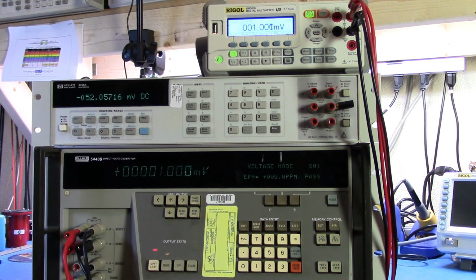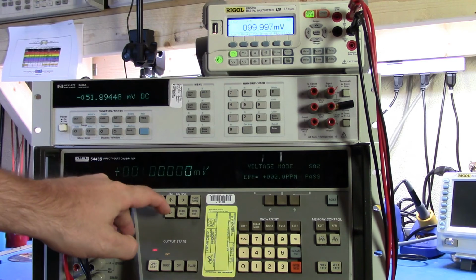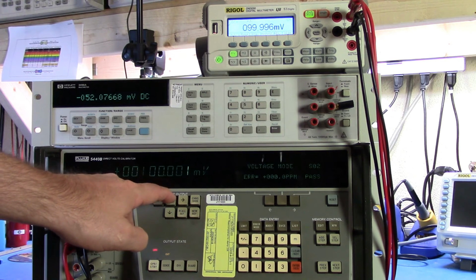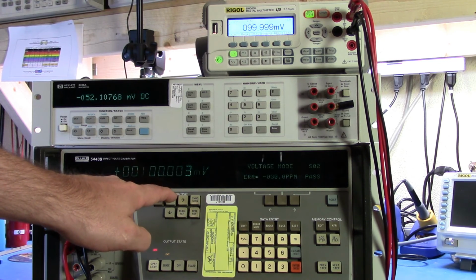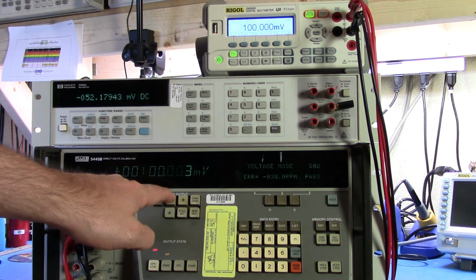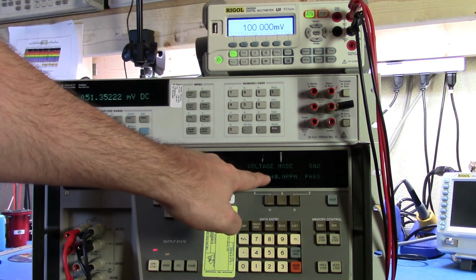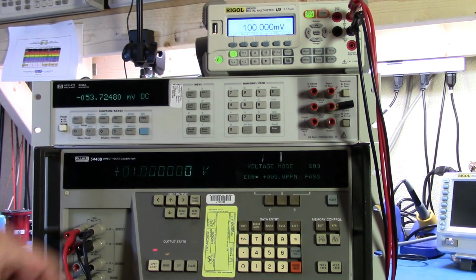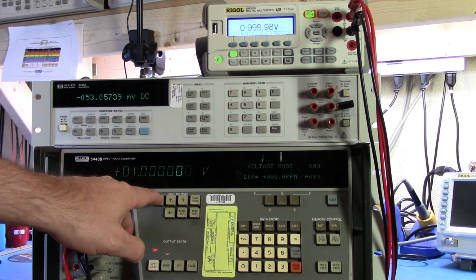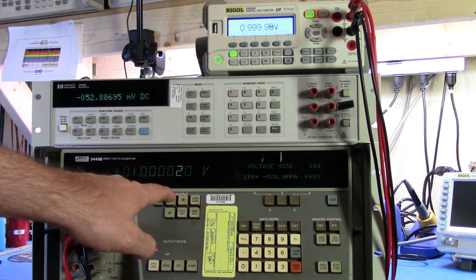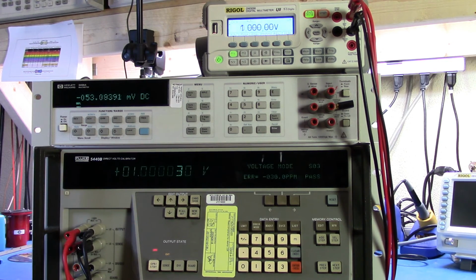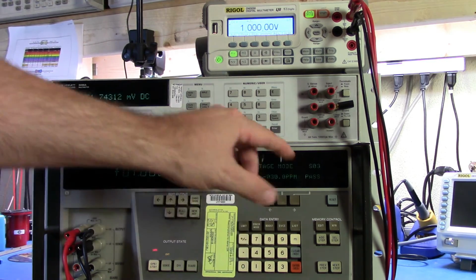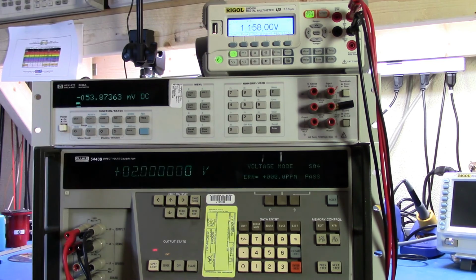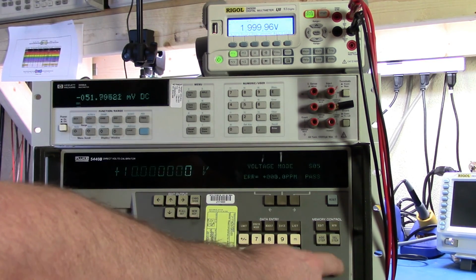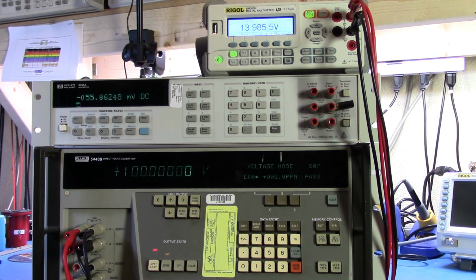Now I can go along to the next step, which in my particular case is 100 millivolts. Looking up here, I can bring that up a little bit more. Now we're at 4, so we're 40 ppm, but we're still a pass. Let's go to my next step. I want to check 1 volt now. Once this settles down, I can bring it up a little bit, and now I'm reading 30 ppm, and so on. I can go to the next step, which here is 2 volts, then 10, 20, 100, and do that same process.